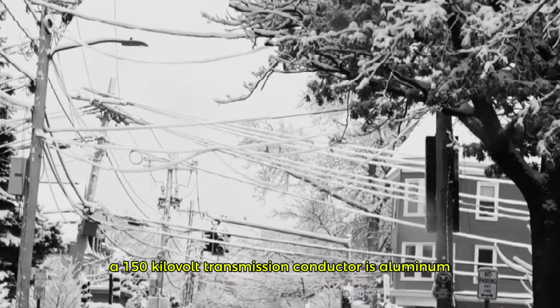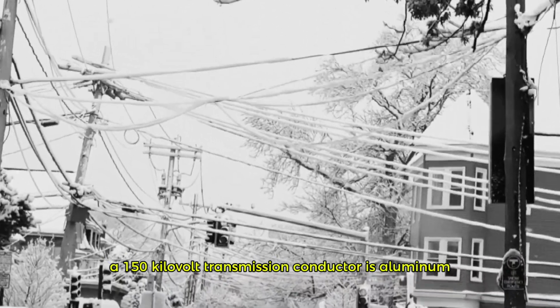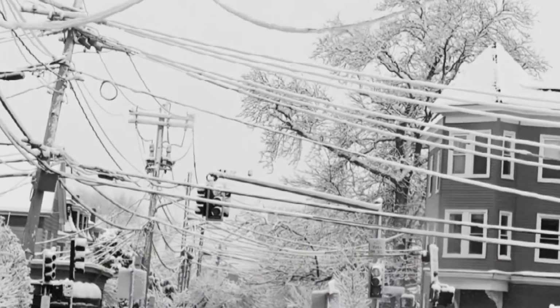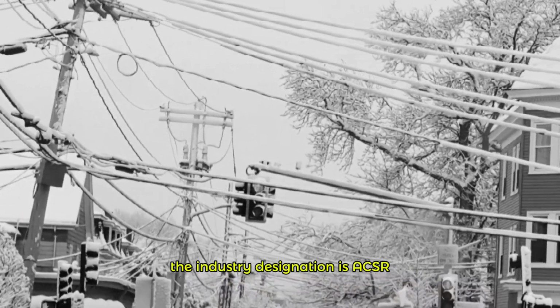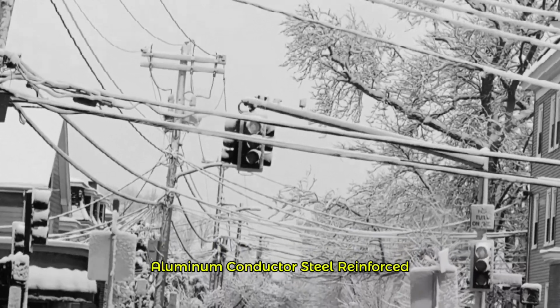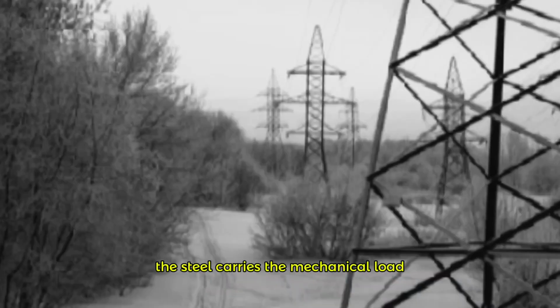A 150 kilovolt transmission conductor is aluminum wound around a steel core. The industry designation is ACSR, aluminum conductor steel reinforced. The steel carries the mechanical load, the aluminum carries the current. The design solves a problem that the first long-distance transmission engineers struggled with from the beginning. Steel is strong but resistive.